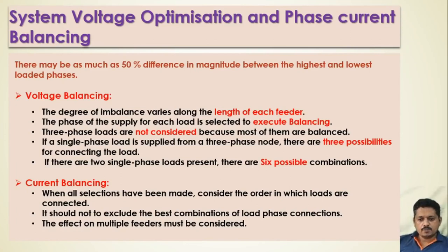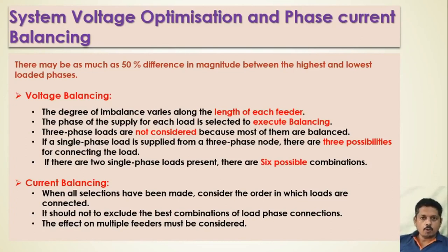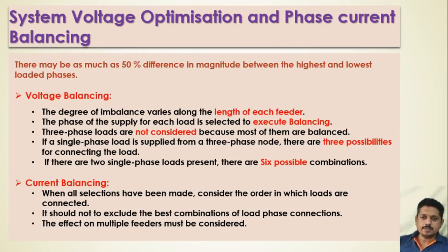The next technique is system voltage optimization and phase current balancing. Voltage imbalance depends on the length of each feeder, so we must consider this and select the appropriate phase for delivering supply to a particular load. We treat three-phase loads as balanced, so we focus only on single-phase loads connected through the three-phase system.